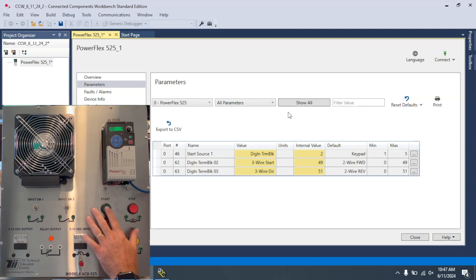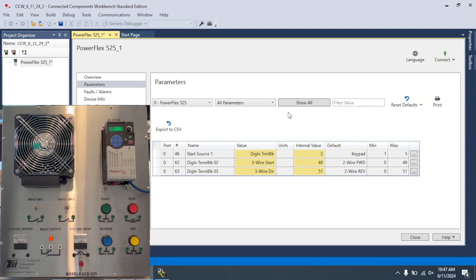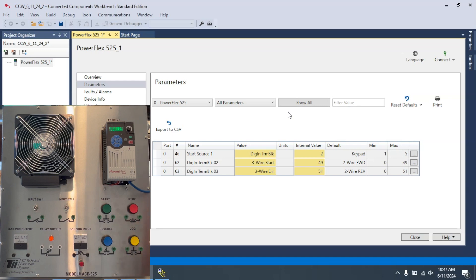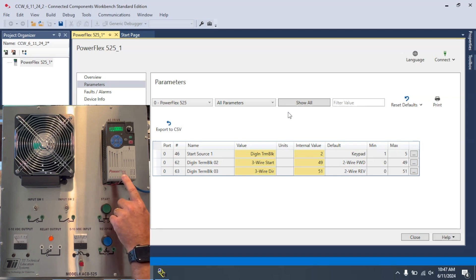Three-wire control, meaning I can push it, step away, let it run up. And then whenever I'm done, I can come here and hit the Stop button. Really pretty simple. And these are the steps that it takes to set up three-wire control using CCW for the PowerFlex 525.